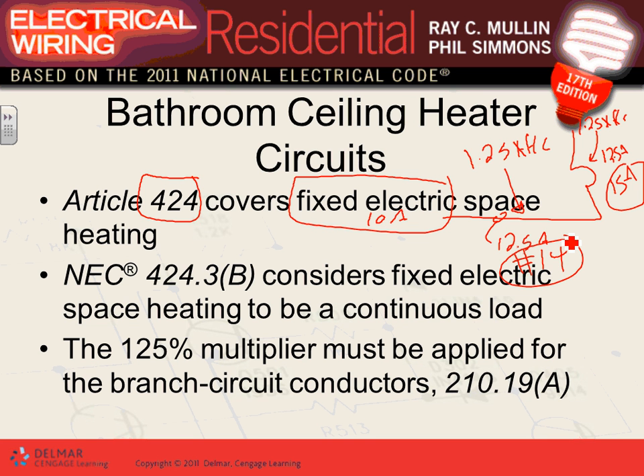Because it's considered a continuous load. That's how we size it. So that's why I told you guys the baseboard heaters that you did will have a dedicated 20 amp circuit to them. But if you want to, I told you 20 amp circuit, because if you go through the math of sizing, yeah, you're going to end up with a 20 amp circuit.